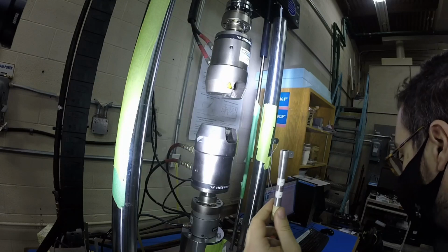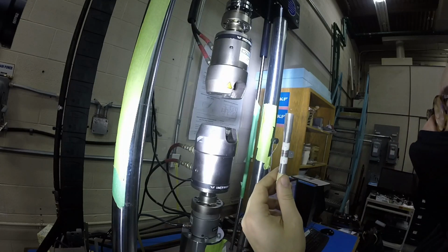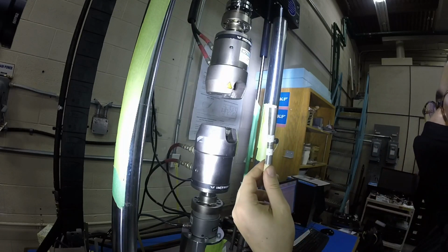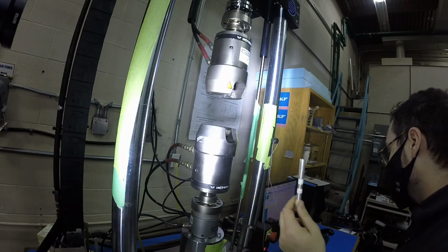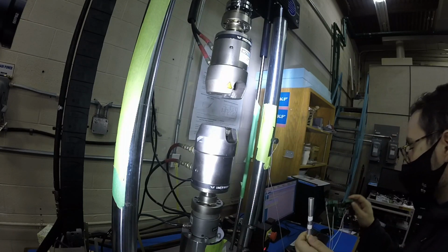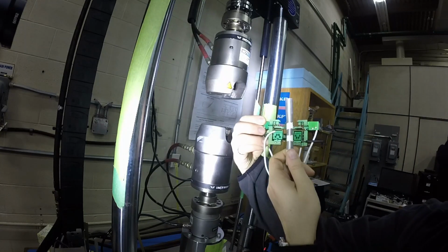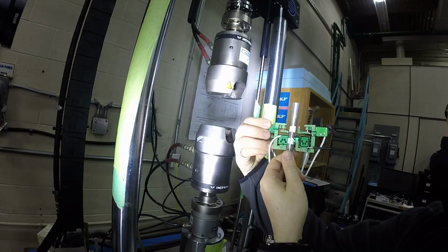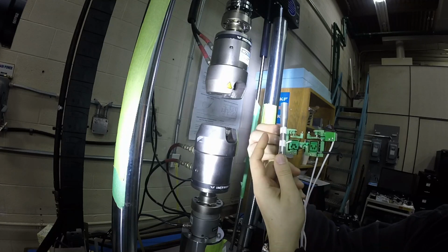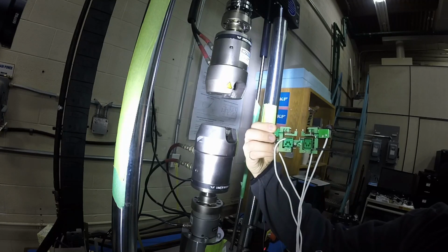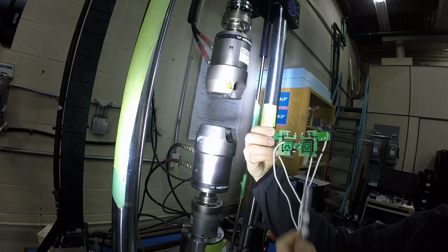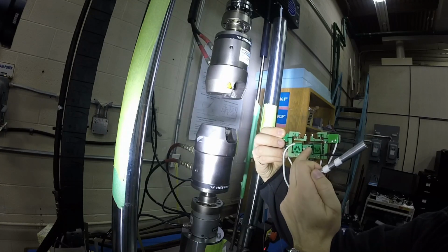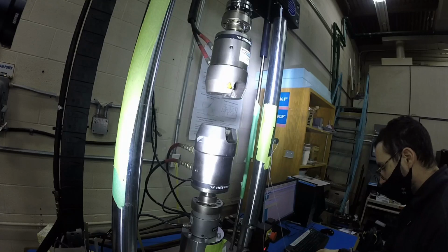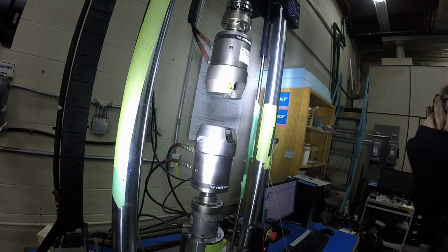dry, and the reasoning for that is to allow the pins that are in the biaxial extensometer to actually bite in to the surface. So you can see the biaxial extensometer right here, and it's going to actually clamp onto that area there. So you want to make sure roughly that you get the coating applied to the correct area on the sample that lines up with the 4 pins that are on the extensometer. You want to be very gentle with the extensometer, obviously. It's a delicate device, and you want to make sure that we don't do anything to damage the extensometer.